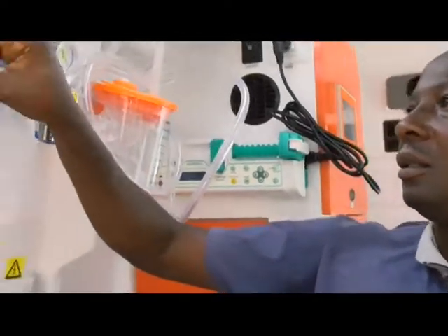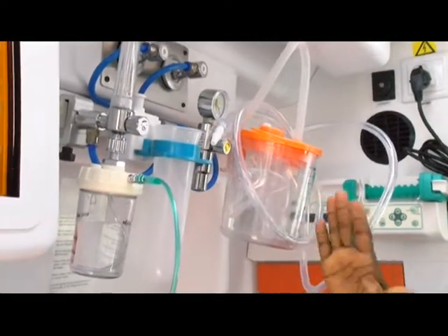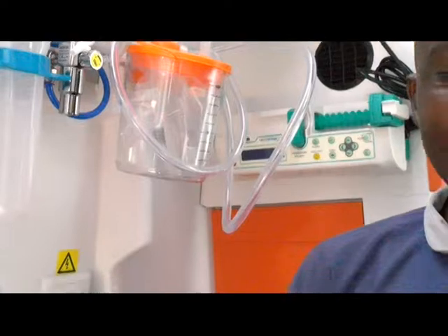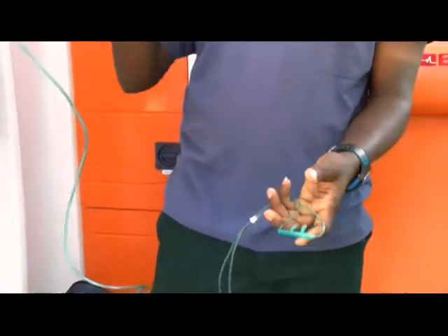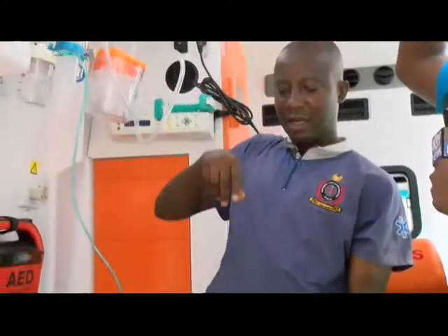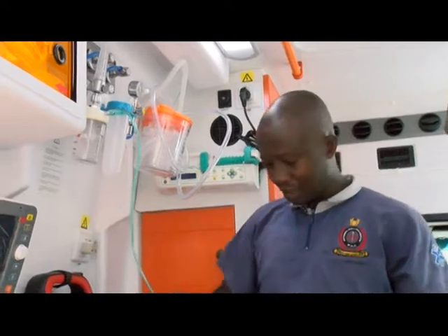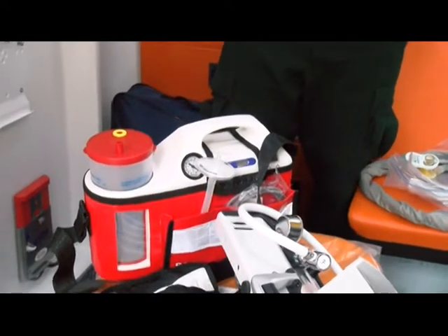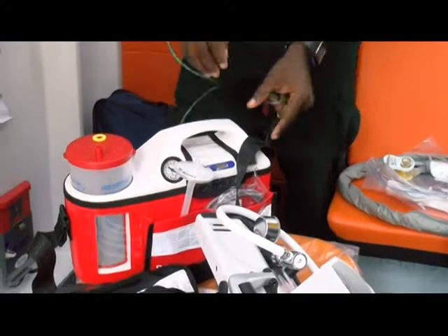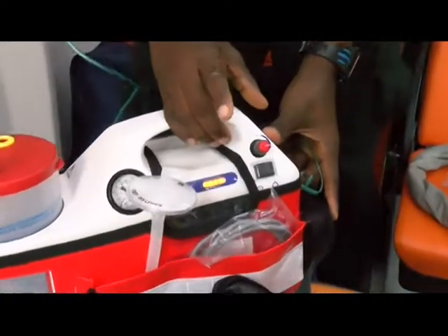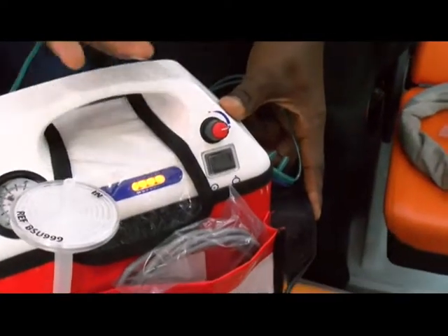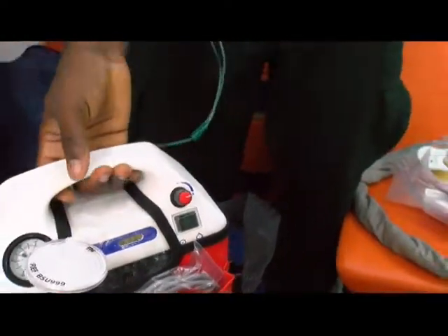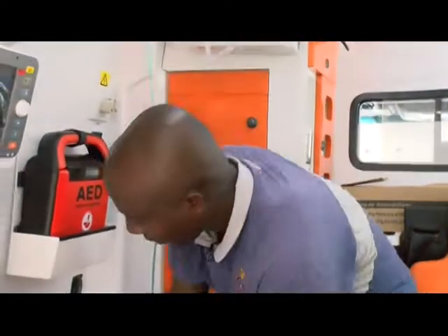So we have oxygen suction units. This is also a suction unit, which helps you when the patient is here and you have to suction. You just connect it to the catheter, then you do your suction. But with this one, this is mobile, this is portable. If the patient is outside, you just move with it and go and do it. You just put it on, then you start using your catheters, and it's chargeable. Check pressure, hose system and gas supply.